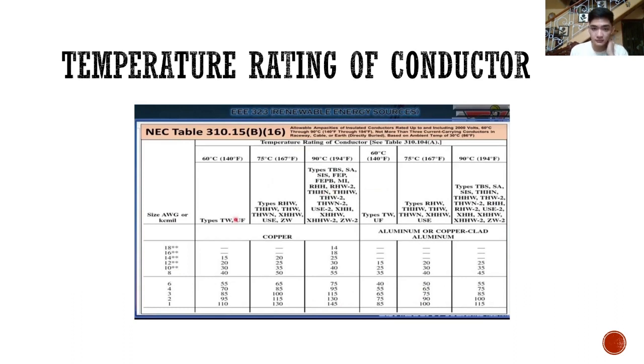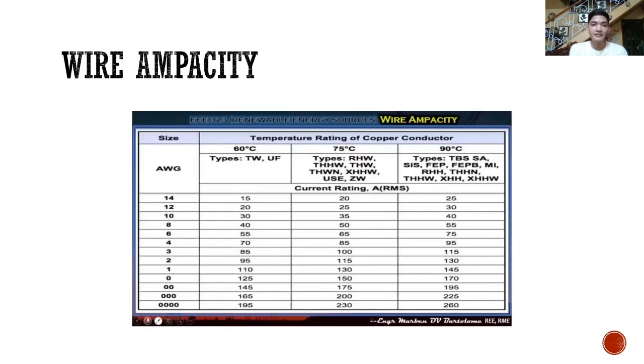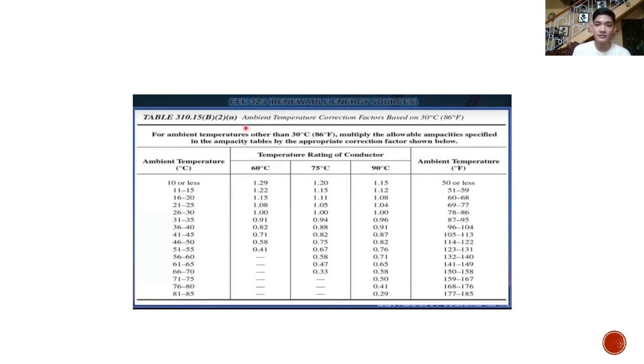Temperature rating of conductor. It is written there. Wire ampacity, temperature rating of copper conductor. For TW at 60 degrees Celsius, 14 American wire gauge is 15. For 12 it is 20. Here at 75 degrees Celsius, the types listed are RHW, THHW, THW. For American wire gauge 14, the size is 20, and for 12, 25. The same goes for 90 degrees Celsius, where the types are also listed. Next is ambient temperature correction factors based on 30 degrees Celsius.